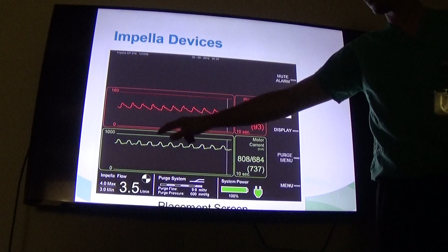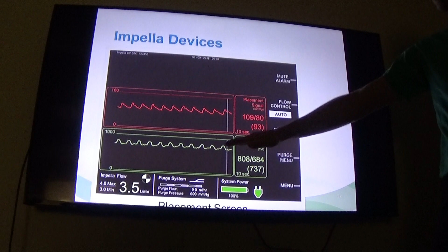Then you have your motor current. Remember how I said it's easier for the motor to pump in systole? Well, you're going to see a dip during systole. You're going to see a rise in the motor current, so it's drawing more power. It actually has to work harder when it's in diastole. The big problem is again, if you're either completely in the aorta, both ports are in the aorta, or both ports are in the ventricle, what you're going to see is a flat motor current, and you know something's wrong. Again, the case we had at Ann's, the patient had a flat motor current, but had an aortic waveform. So we knew something was wrong. We knew there was a problem. And again, just keying into those cues, you can know that there's an issue with the device and it needs to be addressed.